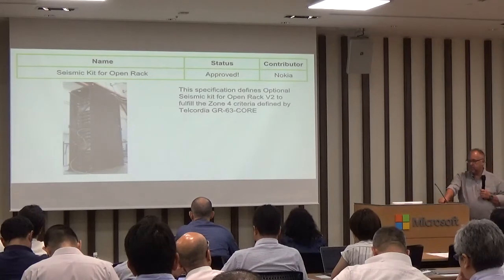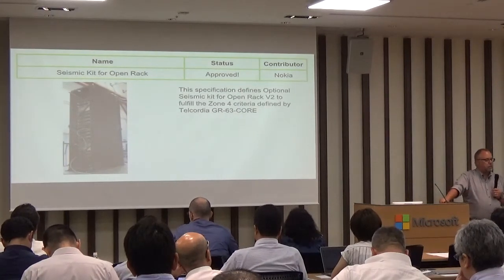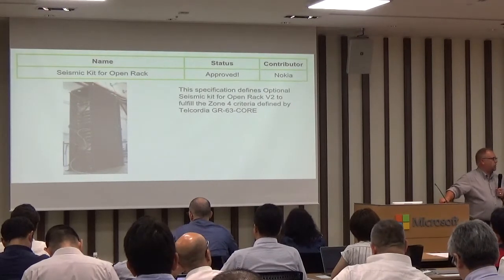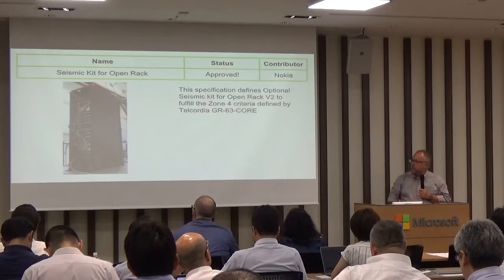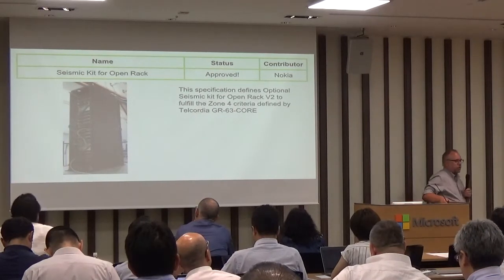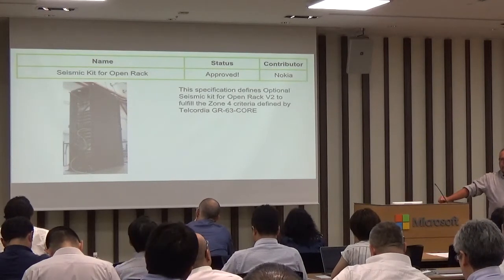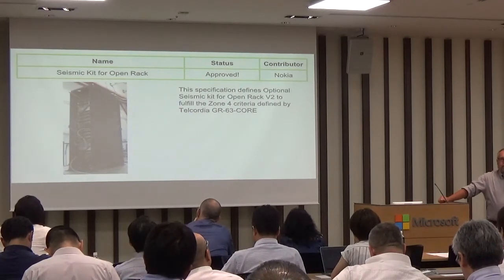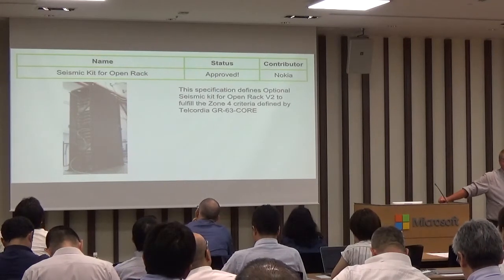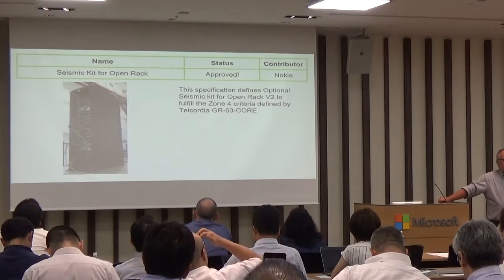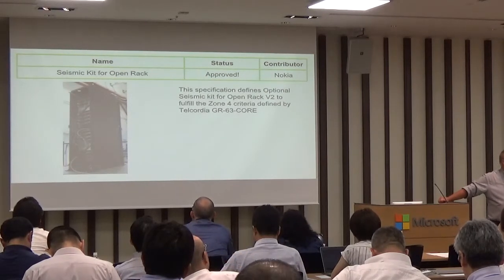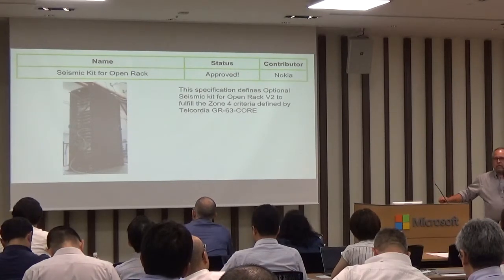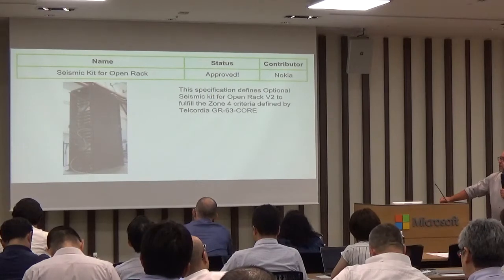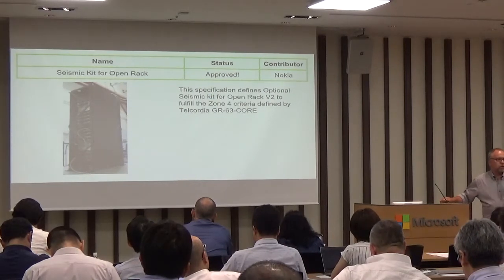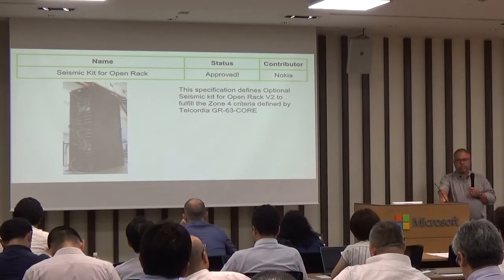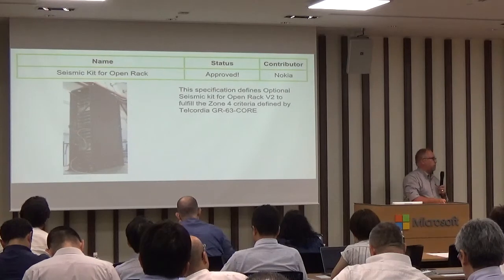This is a contribution from Nokia, a seismic kit that actually bolts on to a standard OpenRack. There are crossbars on the front of the rack and crossbars on the back of the rack. It's a very simple design, yet elegant, in that it solves seismic issues and allows this rack to be deployed into data centers, particularly central offices and telecom data centers that require equipment to meet the GR-63-CORE specifications, specifically the stringent Zone 4 requirement for seismic zones.